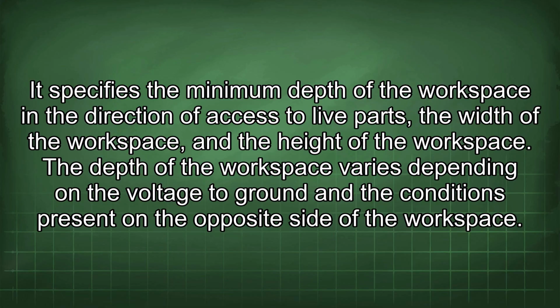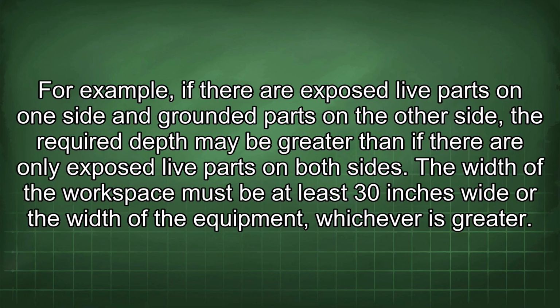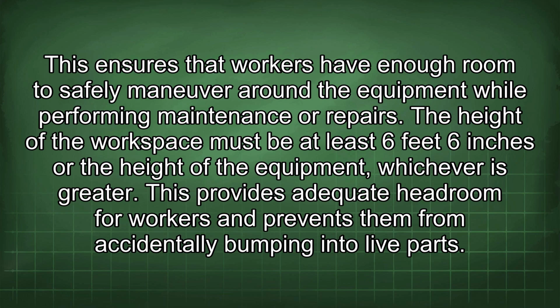The depth of the workspace varies depending on the voltage to ground and the conditions present on the opposite side of the workspace. For example, if there are exposed live parts on one side and grounded parts on the other side, the required depth may be greater than if there are only exposed live parts on both sides. The width of the workspace must be at least 30 inches wide, or the width of the equipment, whichever is greater. This ensures that workers have enough room to safely maneuver around the equipment while performing maintenance or repairs. The height of the workspace must be at least 6 feet 6 inches, or the height of the equipment, whichever is greater. This provides adequate headroom for workers and prevents them from accidentally bumping into live parts.